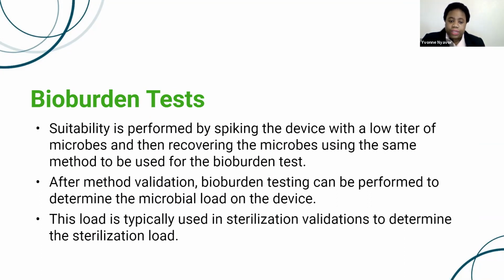So after this validation is performed and we're sure that the testing conditions can give us reproducible results, we will go ahead and perform bioburden testing to determine the microbial load. So you're plating and then you're growing out the colonies. And then typically we will use this load in sterilization validations if needed, just to determine the sterilization load.